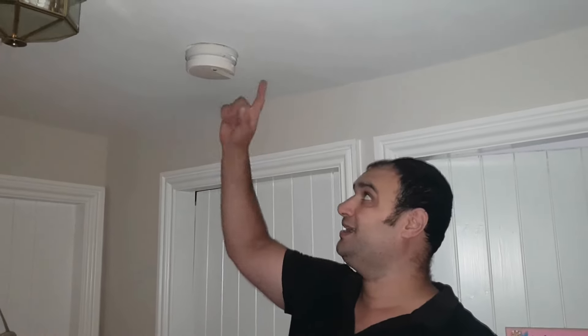As you can see, we've got a Kidde KF10 smoke alarm here on the ceiling, and the customer within this property has complained that it's bleeping regularly about once every minute. This is usually an indication that the battery backup within the smoke alarm has failed. It doesn't last forever — the idea is to provide power to the smoke alarm in the event of a power cut so that it still functions.